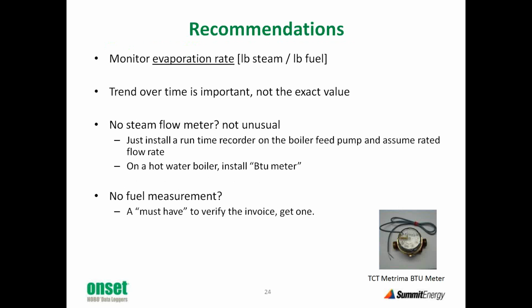My recommendation, monitor the evaporation rate. How many pounds of steam did you get per pound of fuel? And target that. Figure it out once a month, set a goal, and make sure you're managing to that level. Now, easier said than done. We don't know what our steam flow is. We don't have a steam flow meter. That's not unusual. Most boilers do not have steam flow meters.